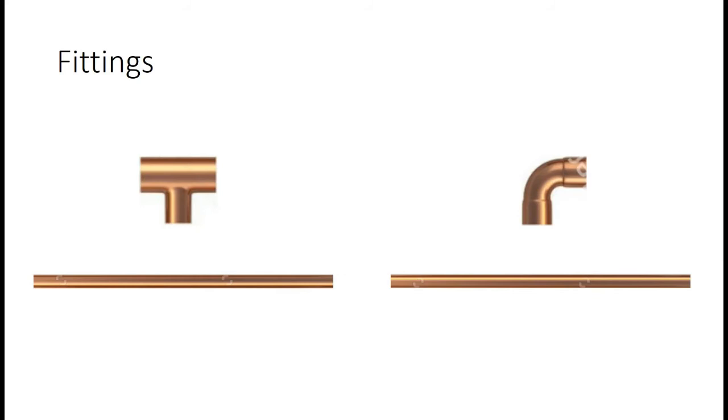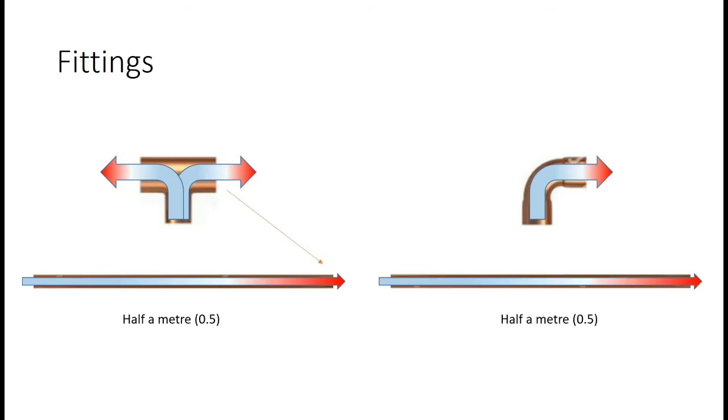In all gas systems, we have fittings and they usually take the form of T pieces, which split the gas, or elbows, which turn the gas by 90 degrees. Both of these turn the gas very sharply. And when they turn it, they take away energy from it and they reduce the pressure. Now they reduce the pressure by an equivalent of half a metre of straight pipe.